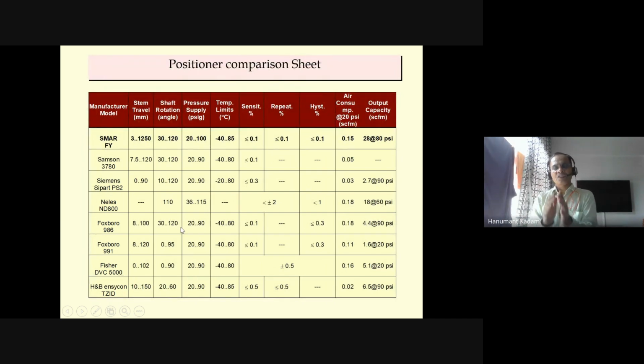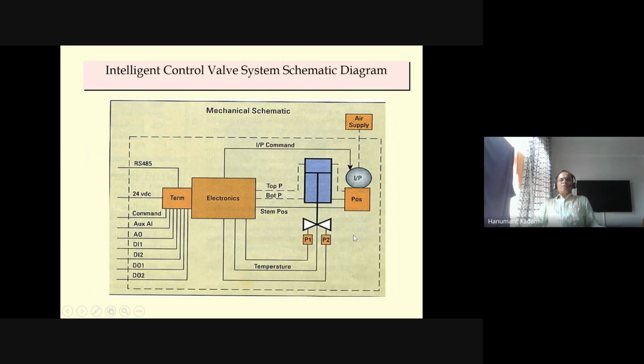Then this is what is related to electronics. Furthermore, about the mechanical part: stem travel, shaft rotation, pressure supply, temperature limit, sensitivity, repeatability, hysteresis, air consumption, and output capacity. These are the additional specifications for the smart positioners. So this slide is very, very important to understand the valve positioners. We can say smart valve positioners.